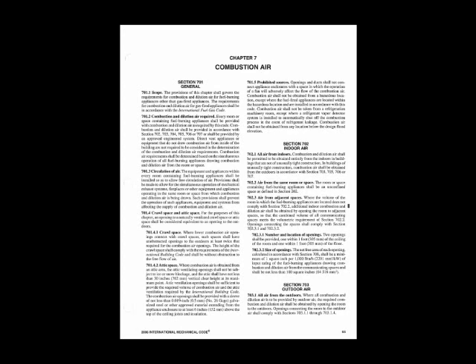In this lesson, we're going to talk about both chapters 7 and 8 of the International Mechanical Code. The reason I'm combining these lessons is because it all has to deal with combustion. The combustion air in chapter 7 is the air coming into the furnace, how we're getting the air that's required for combustion to occur. Chapter 8 talks about the chimneys and the ventilation, that is the air leaving the furnace. It's great to have these together because they must be balanced. I must have a certain amount of air for combustion, and then the air has to be able to leave the building without mixing with the inside air.